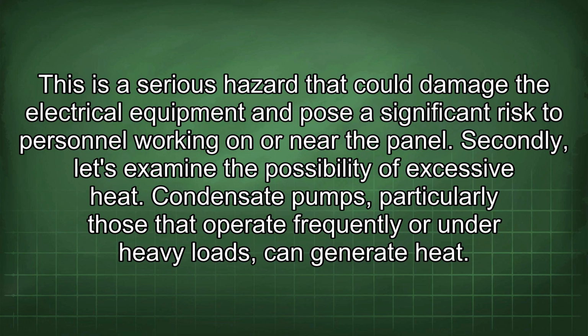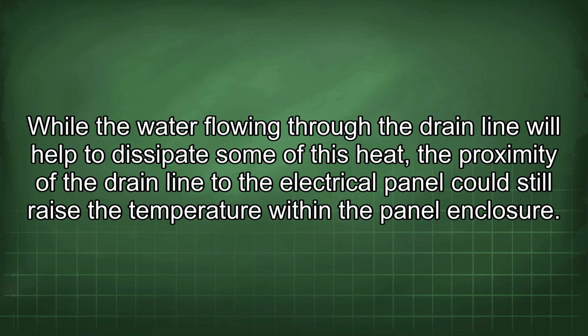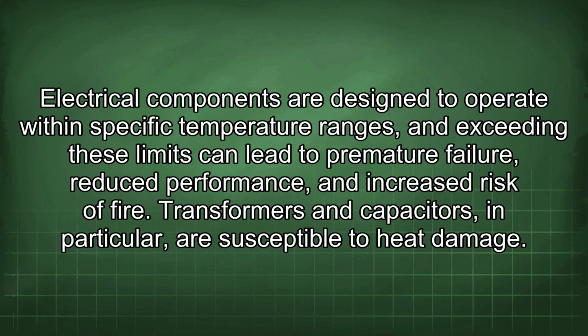Condensate pumps, particularly those that operate frequently or under heavy loads, can generate heat. While the water flowing through the drain line will help to dissipate some of this heat, the proximity of the drain line to the electrical panel could still raise the temperature within the panel enclosure. Electrical components are designed to operate within specific temperature ranges, and exceeding these limits can lead to premature failure, reduced performance, and increased risk of fire.